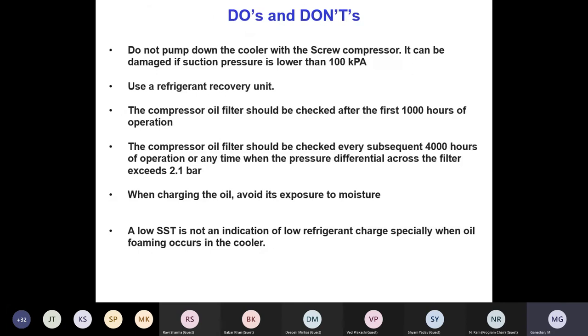Do's and don'ts. Do not pump down. Never use a screw compressor to pump down. Pumping down is a different thing; there are evacuating kits and a vacuum pump. You should never use a screw compressor because a screw cannot do the function of evacuation. Within no time, catastrophic failure can happen. It can seize the screws. Do not use it. Use only a recovery unit.